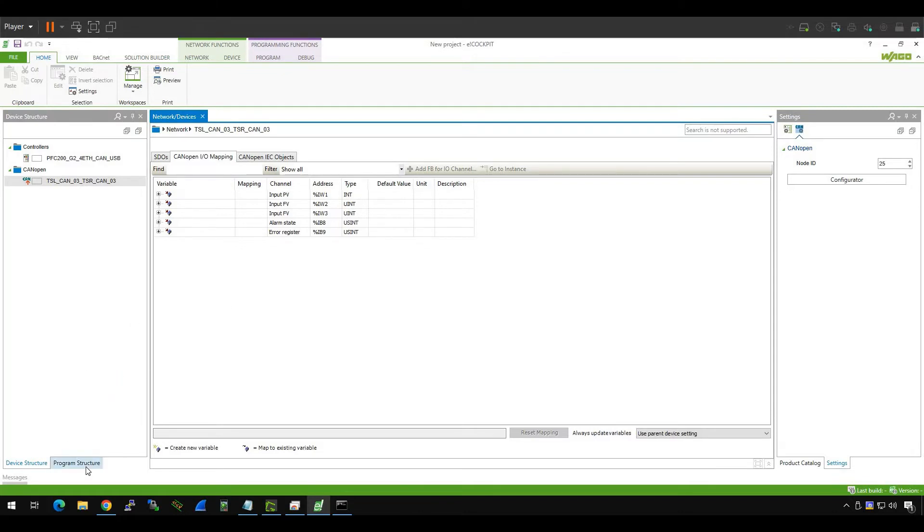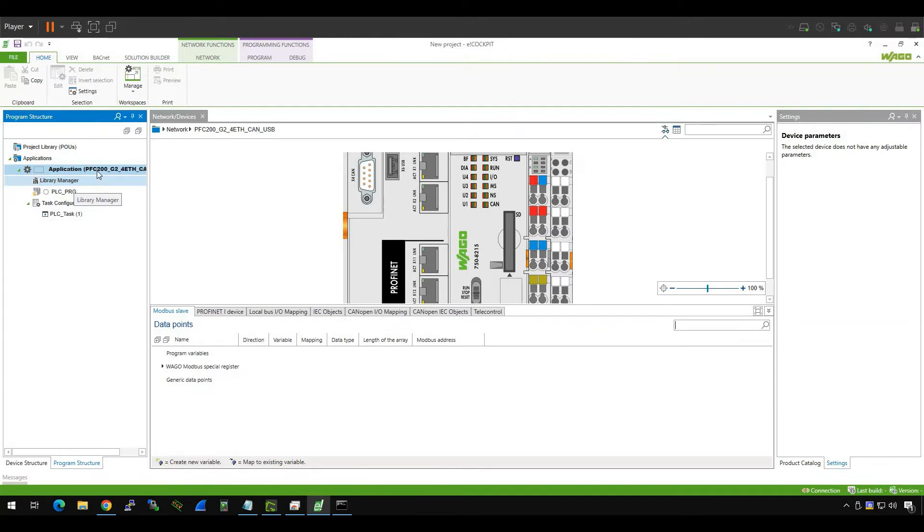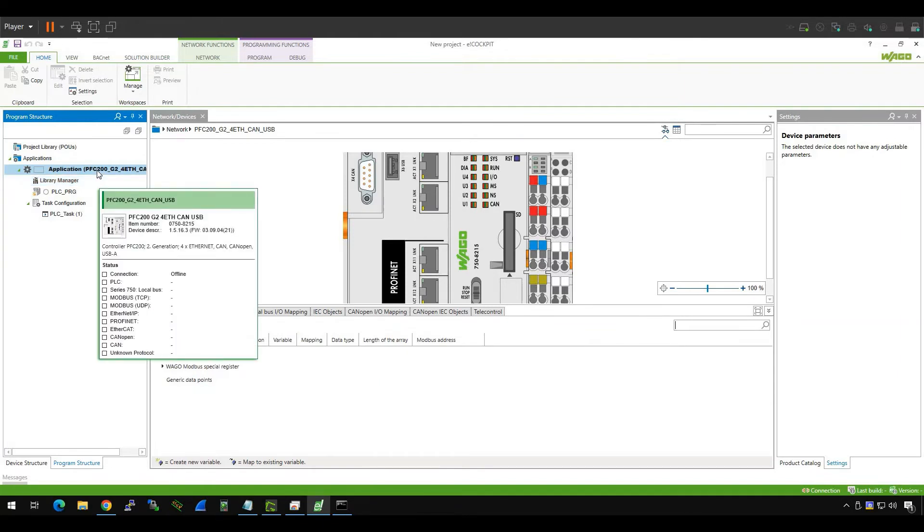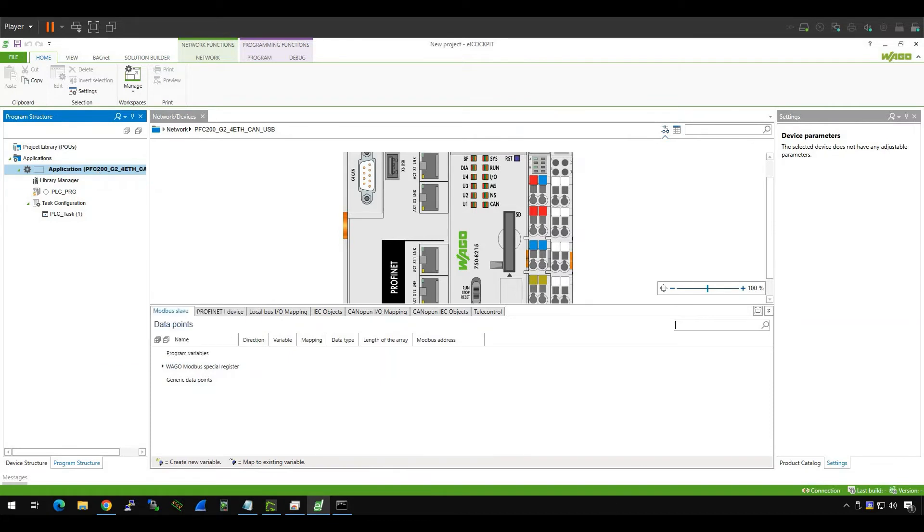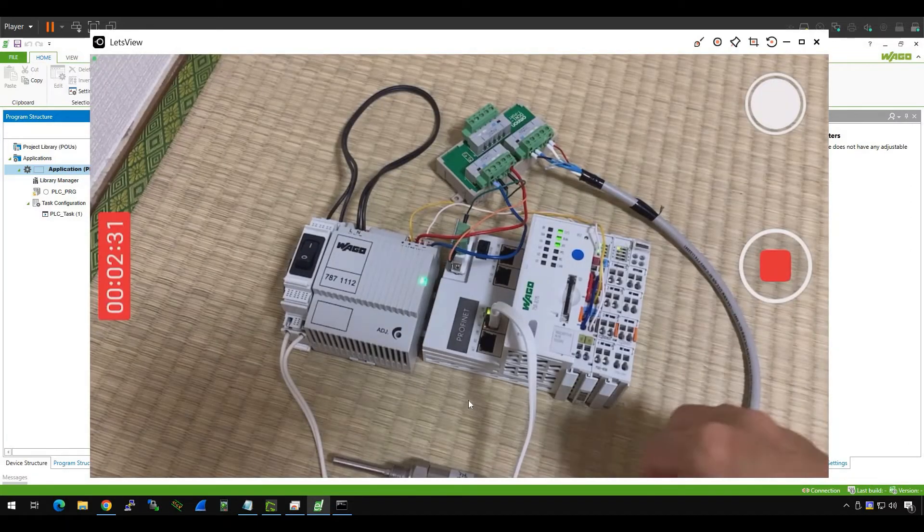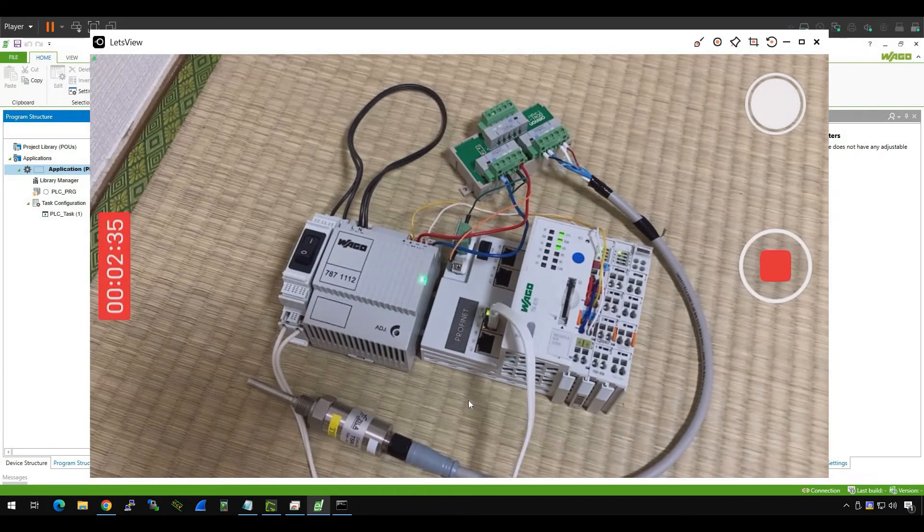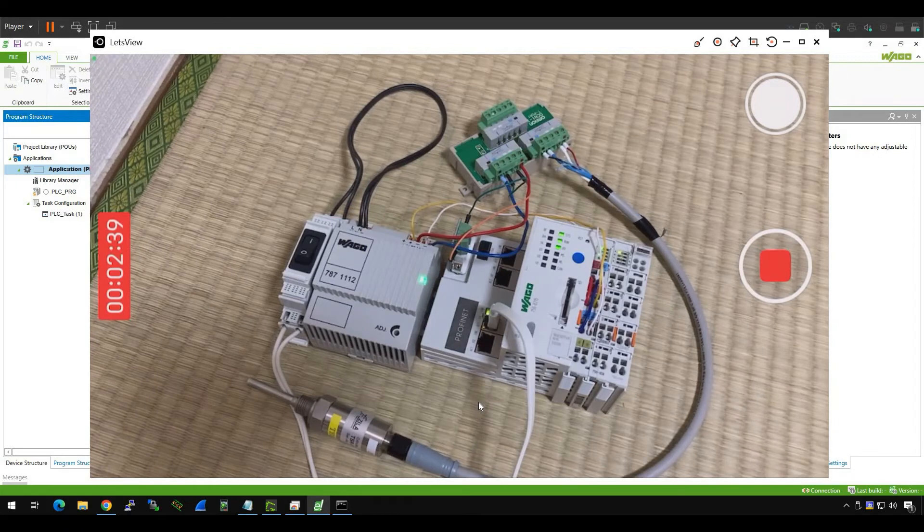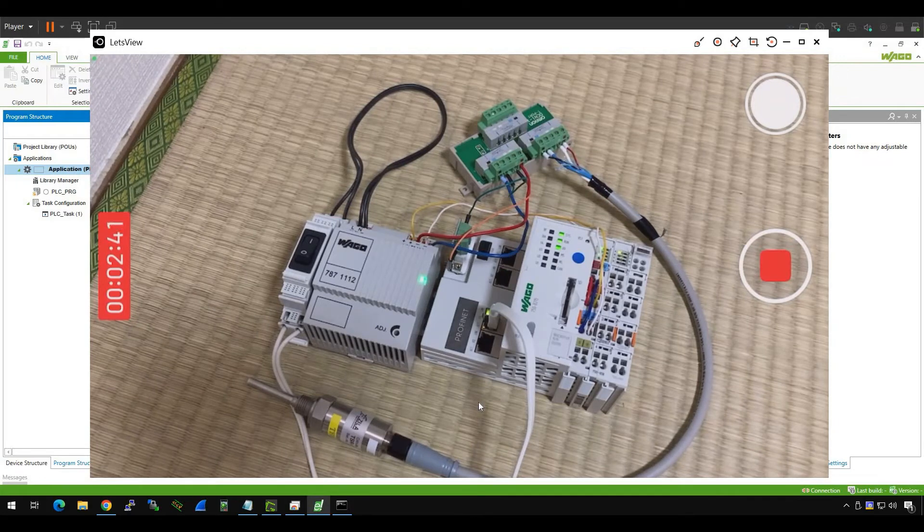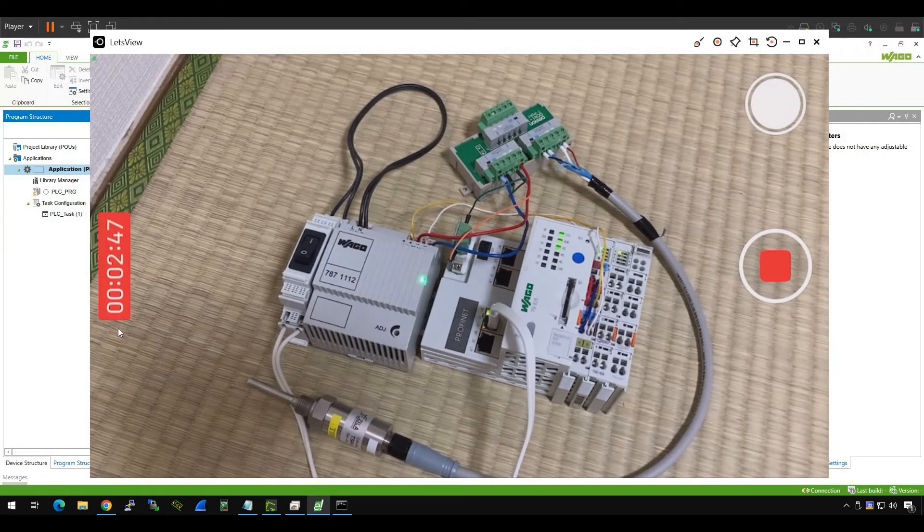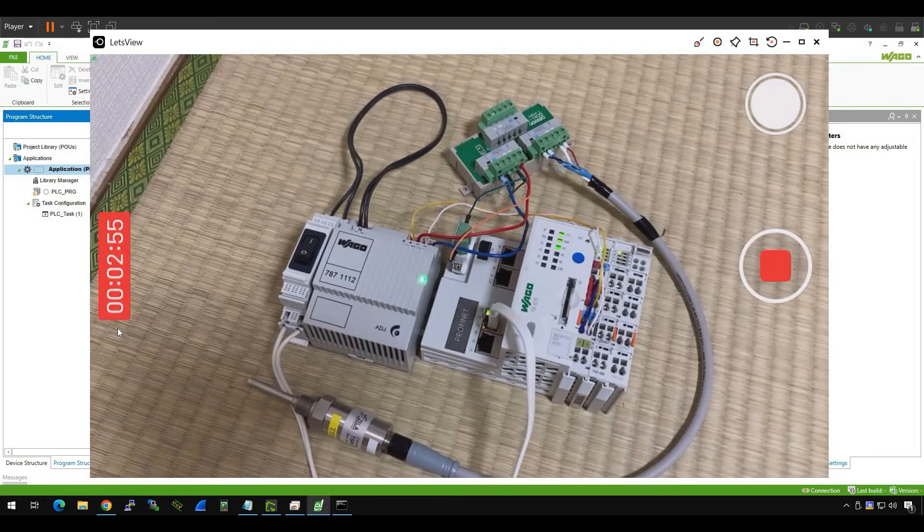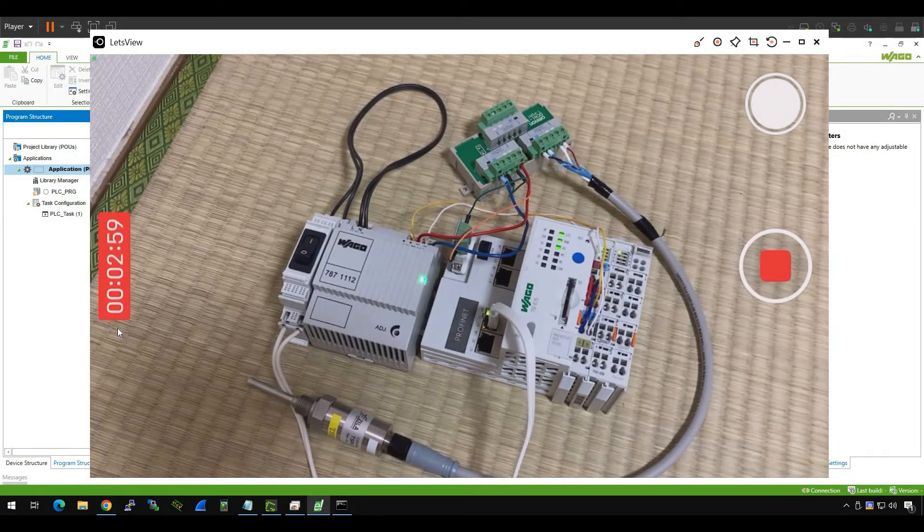Go to the left hand side and program structure. Then you can see here, it's a little bit like CodeSys if you've used CodeSys before. Because e!COCKPIT is actually a front-end engine that CodeSys feeds upon. So it's the same. And then I'll create a DUT first. DUT is data unit type. Although now in my case, I only have one sensor, but what happens if I have two or three or four sensors? Do I need to create all the variables one by one again? No, I don't want to do this. It's not convenient and very difficult for naming. So what I always do is create a DUT, data unit types, to group many variables into one variable.